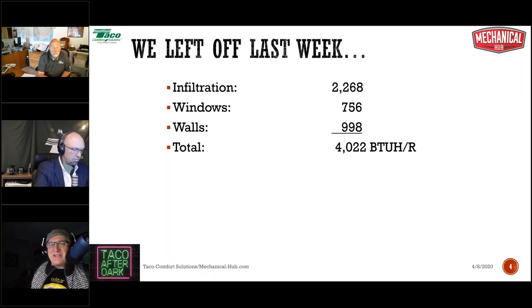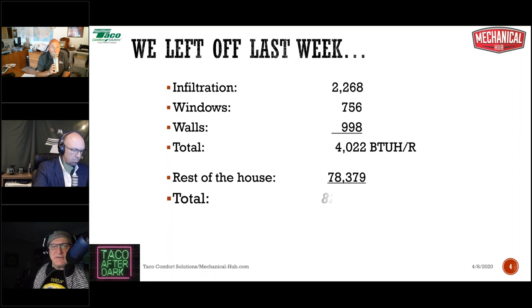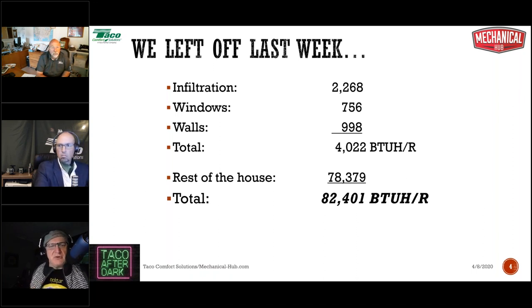And then we quickly did the rest of the house, and we came up with a heat load of 78,379 for the rest of the house, for a total BTUH required of 82,401. So that's the total BTU load that we have to deal with when we go about sizing our boiler. That's one of the things we're obviously going to look at. From this point on, we're going to use that one room number, 4,022 BTUs, and look at what we might do for heat emitters and understanding things.